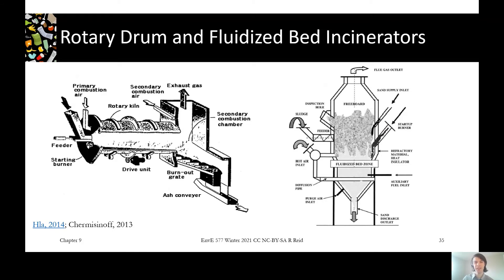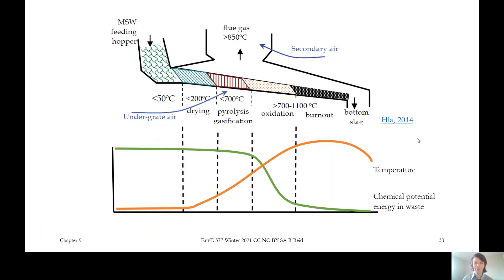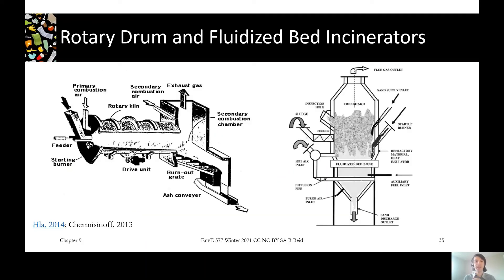In addition to the moving grate style reactor, where waste moves down like an escalator, there are other reactor types also aimed at achieving the three Ts: time, turbulence, and temperature. Rotary drum and fluidized bed reactors are other styles, more often applied for hazardous waste requiring very good burnout, or for very wet waste like wastewater sludge and leachate that needs good mass transfer to vaporize water. These styles achieve the same goals but use spinning motion or a constantly moving fluidized bed to create turbulence, rather than the moving grates typical of mass burn incinerators.